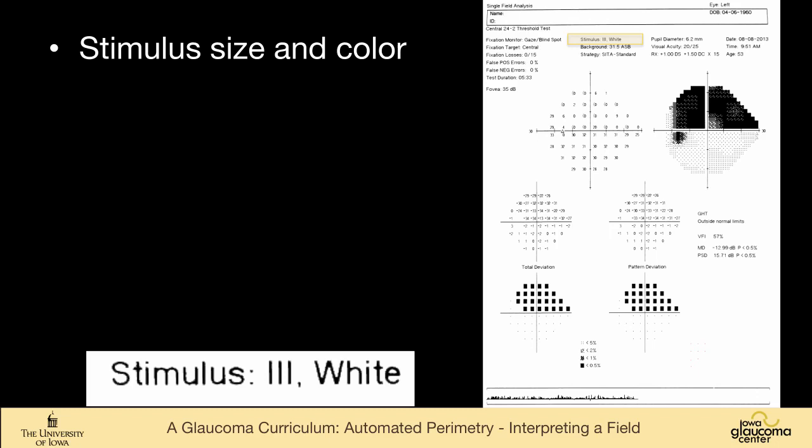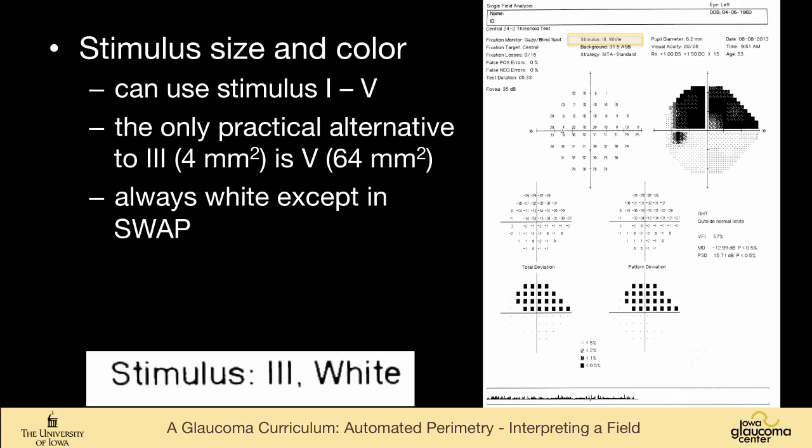Stimulus size and color, this is stimulus size 3, white. You can use anything from Goldmann size 1 to Goldmann size 5. Really the only practical alternative to the size 3, which is 4 square millimeters, is the size 5, which is 64 square millimeters. We always use white-on-white, achromatic field, unless you're doing short-wavelength automated perimetry, which is blue-on-yellow.